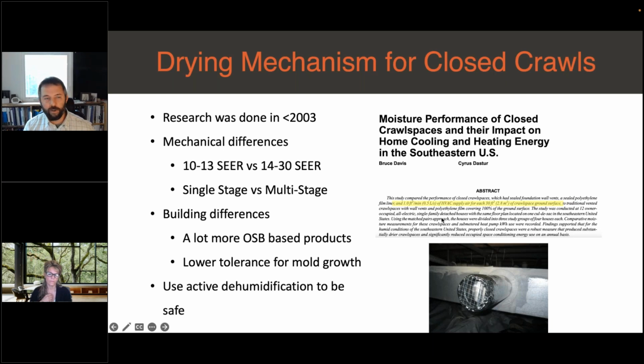The original research, done by my previous employer, Advanced Energy, calls for 1 CFM per 30 square feet. This was determined by field testing sites and modeling done in 2003. A lot has changed in construction since then. We've got more efficient equipment being used, single-stage versus multi-stage is much more prevalent, and we have a lot more OSB being used in these crawl spaces, especially with I-joists.